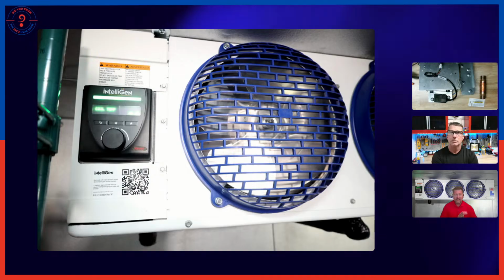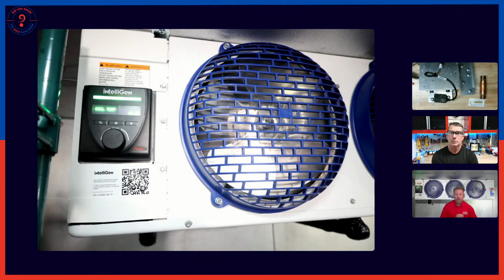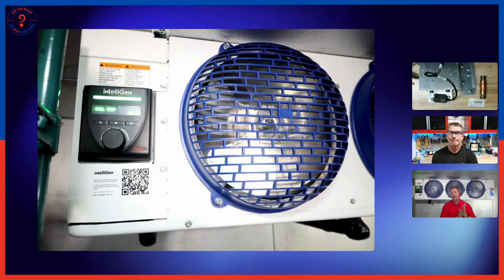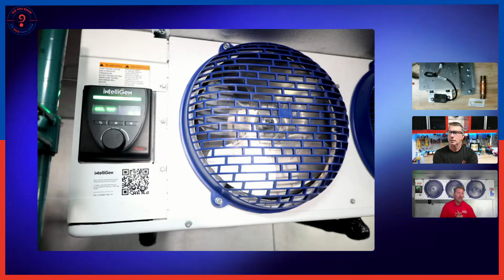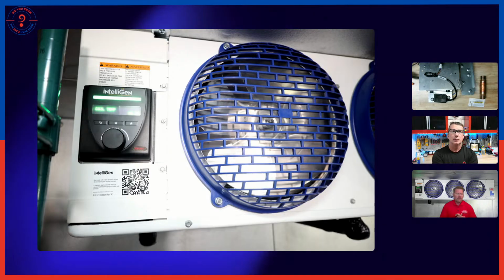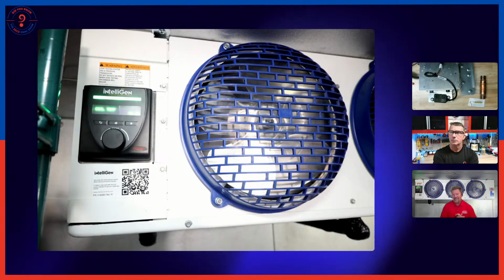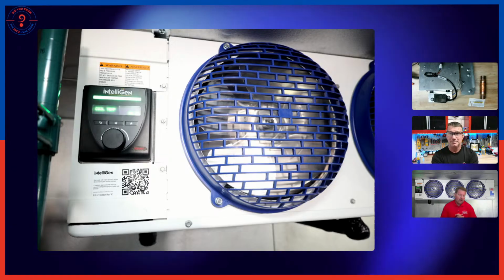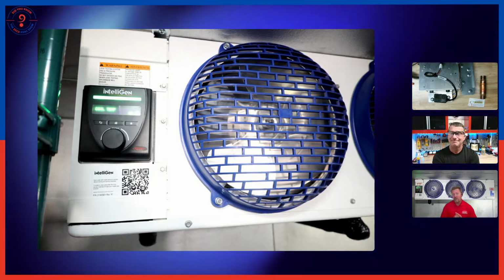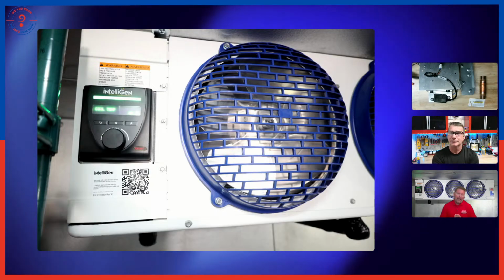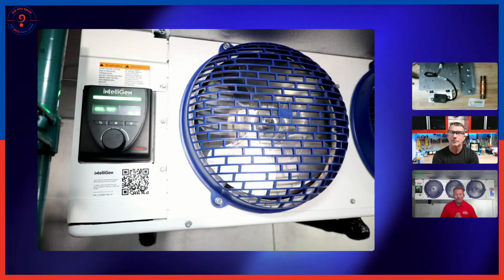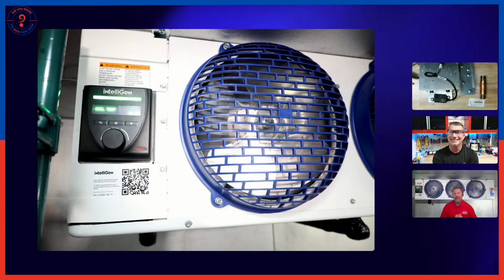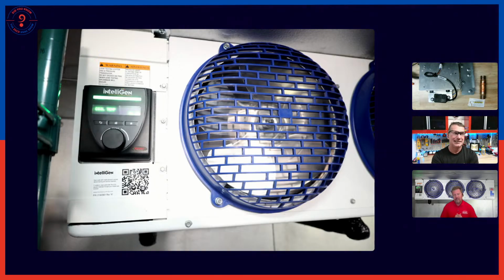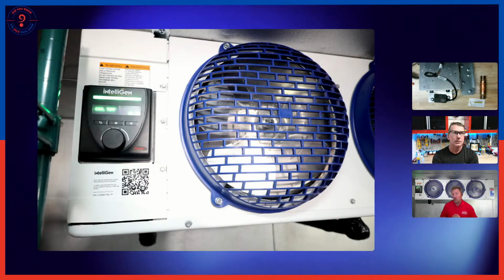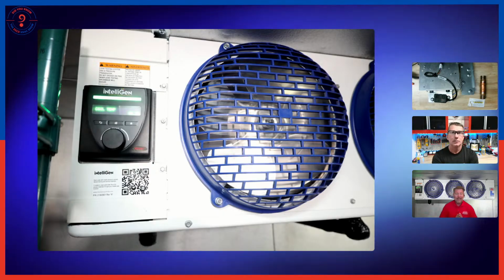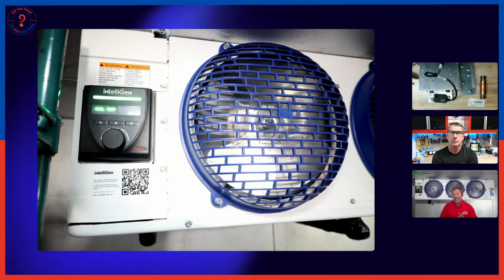We send a 24-volt voltage signal up to the condenser, which activates the controls. But very simple system. We've been using electronic controls now since the late 90s. It was introduced with Beacon 1. Beacon 2, we saw vast improvement with. Now Intelligen, I sometimes call it Beacon 3.0. I hope that my engineers don't hate me for that, but it does function very similar to Beacon. We've just added a whole lot of other great things that it can do. One of them being, and Beacon 2 had this also, refrigerant selectability.